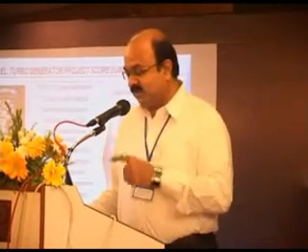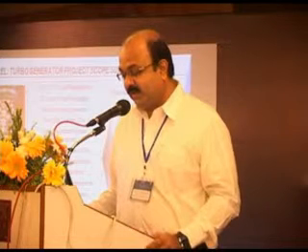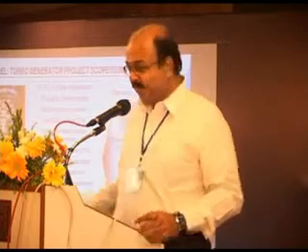So these were the modifications: LP IP turbine replacement, oil system upgrade, overhauling the governors, ESVs, control valves, drains and extraction system refurbishment. So almost the entire thing, including controls, instruments, governing systems. Are we supplying spares for LMZ? Governing systems, I am not sure where they got it from. We are not supplying the spares. We would have gone to the OEM probably to get that. But we have done the refurbishment.